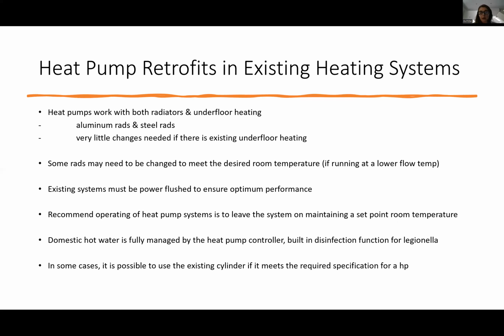And then in terms of how we operate heat pumps, we would recommend that they're left to maintain a set point room temperature rather than run on a schedule, like the way we run our oil and gas boilers. So rather than getting up in the morning and turning it on for an hour and leaving it off all day while you're at work, and coming home and turning it on and turning it off, we say run it on a set point, maintain the desired room temperature, and while you might be running it at a lower background temperature, you'll have a very, very comfortable ambient temperature all day long in your house. So the comfort levels are generally improved greatly when you use heat pumps in this way.